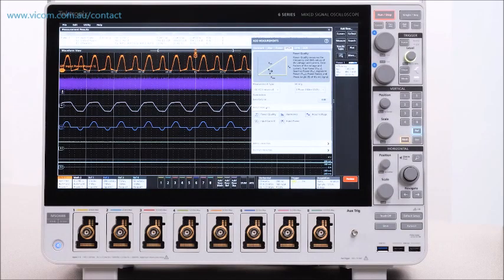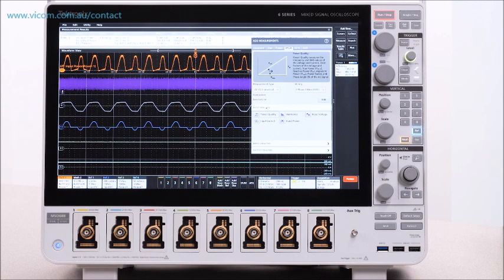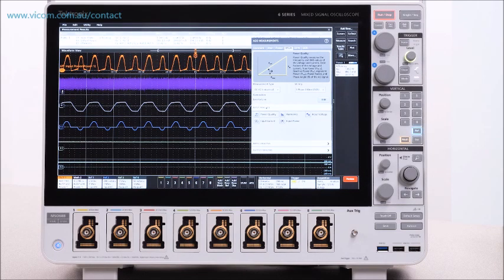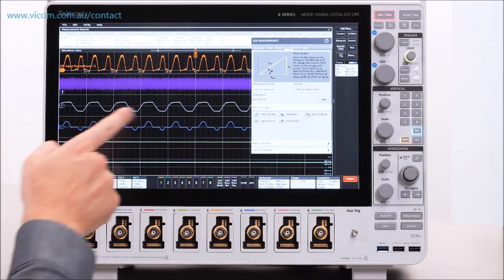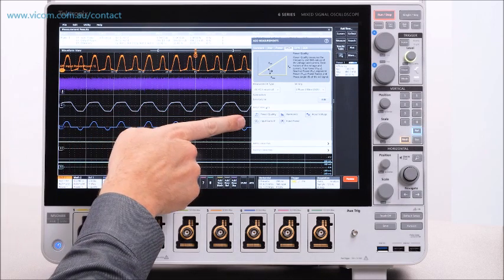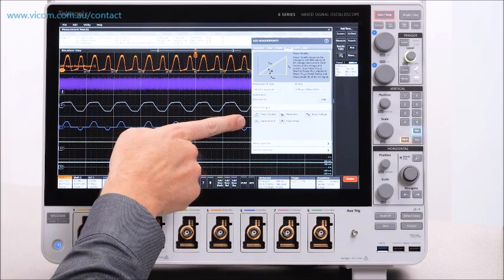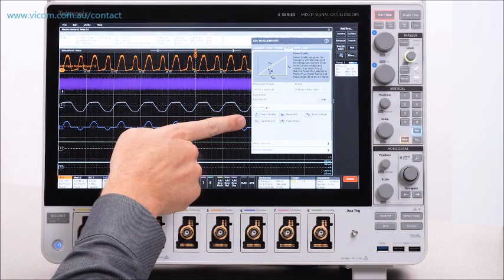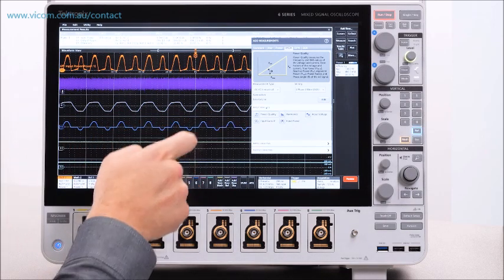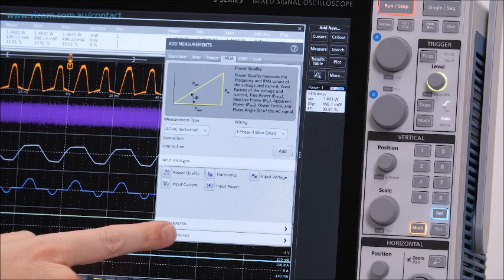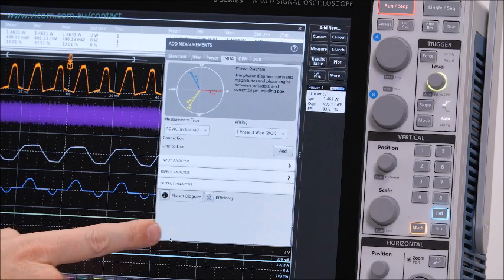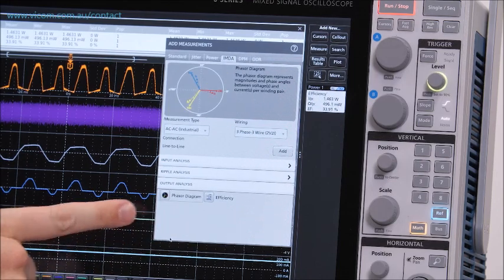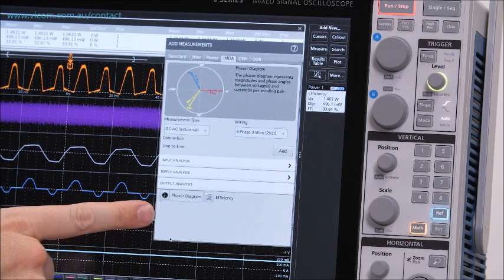For analyzing 3-phase systems, the inverters, motors, and drives measurement package greatly simplifies measurements. Make 3-phase power and power quality measurements, analyze harmonics, and on an 8 channel instrument, you can measure efficiency using the 2 watt meter method.